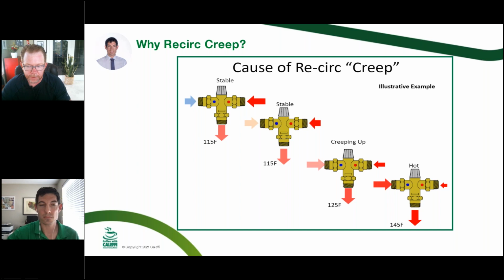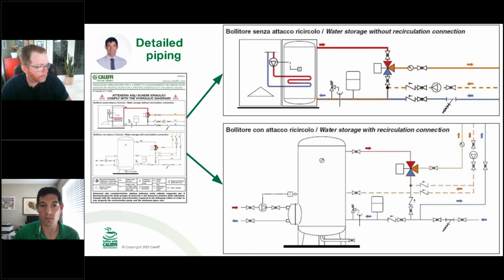One of the questions that came up, Max, and it's a good one, is would an aquastat solve that problem? It can. One of the weird things is that there are some places that, like OSHA is saying, do not use an aquastat, because then you're not recirculating warm enough water. So there are all these different kinds of stakeholders weighing in on how to do this differently. And an aquastat would be helpful, because then your recirc gets up to that temperature and it will turn the pump off. But now you're stagnating all night until that temperature drops. So it can help in one spot and maybe create another issue in another spot. So the better way to do it is to pipe it differently to prevent that creep, with or without the aquastat, depending on what your local rules are.